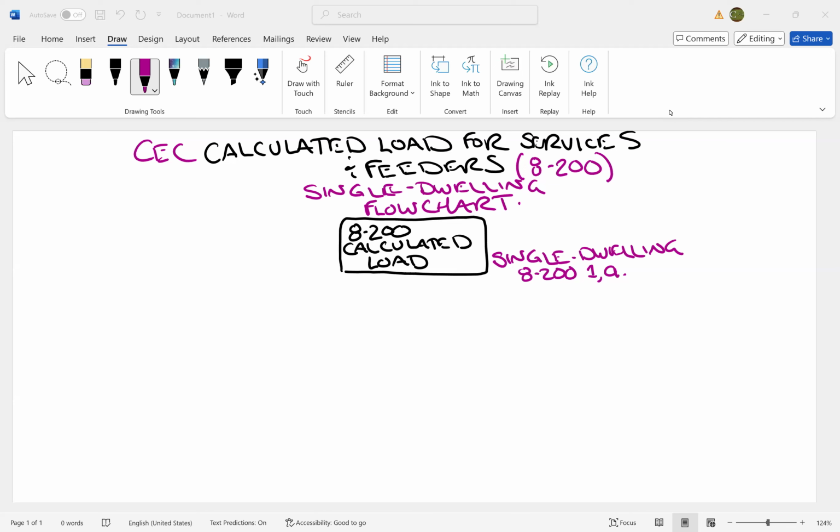Electric range above? Did you have one? Or no electric range? Because it's different if you have an electric range in this house already and no electric range. If there was an electric range, then you're going to have only a demand factor of 25% for more loads above 1,500 watts. Then we'll have a 25% demand factor.